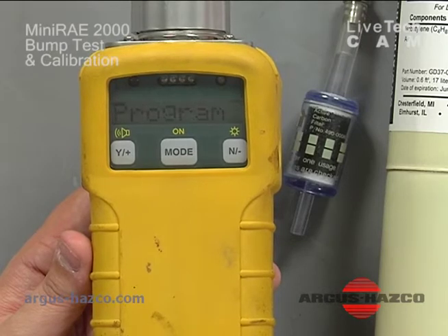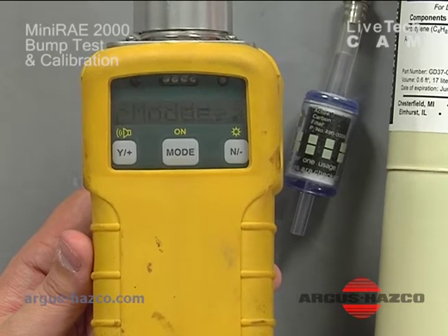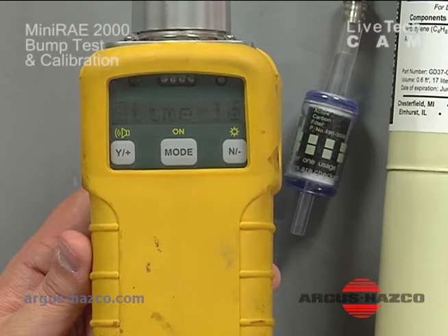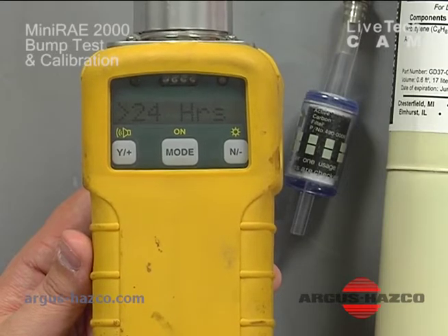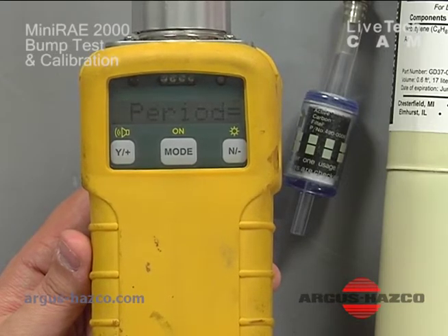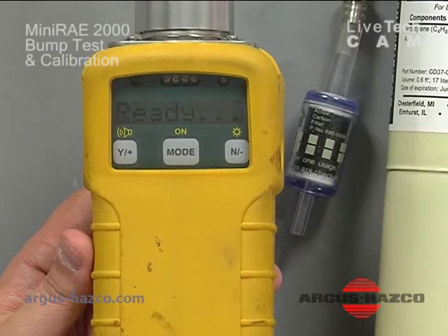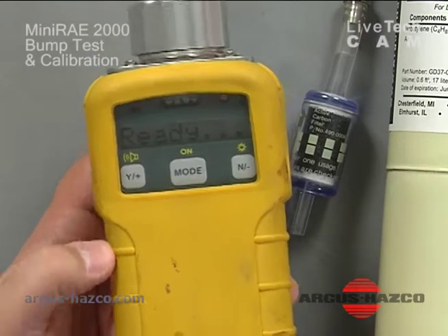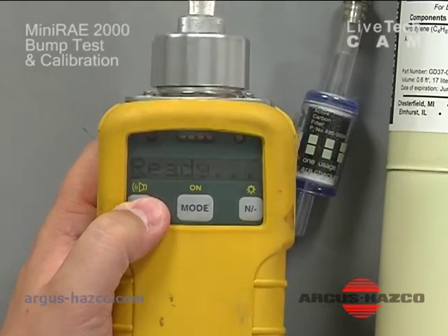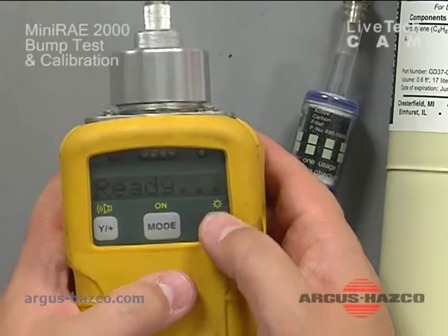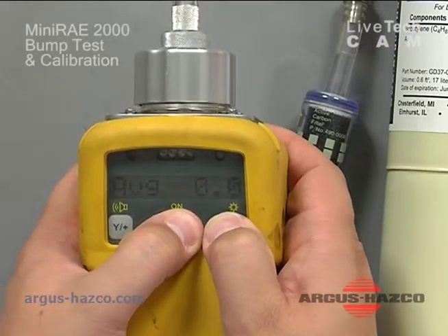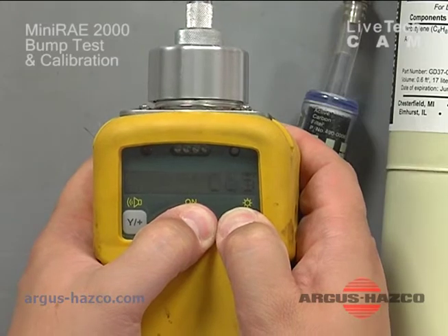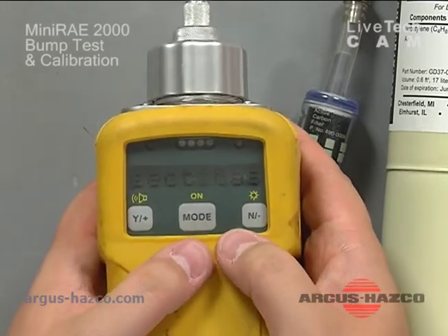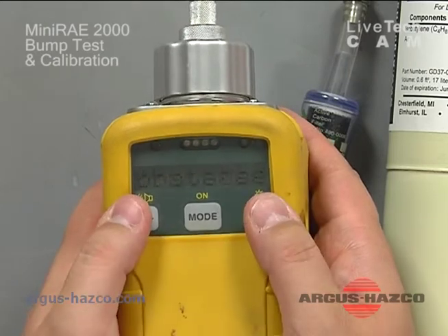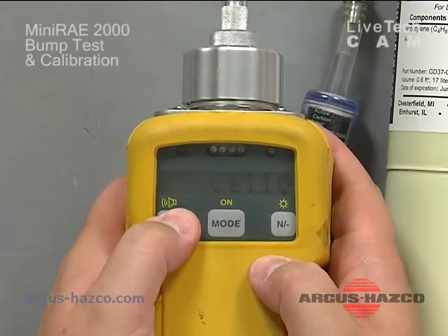The user mode is in program. The alarm mode is in auto reset, so if it hits alarm and drops below that, it will automatically reset. The data log time left is 24 hours if your period is set at 60 seconds. It's going to click over and tell you it's ready to go. You can either hit yes and go in and start your monitoring, or at this point we want to do a fresh air 0. So you take your no minus button and your mode button, and press and hold those together for a few seconds. You'll see a screen come up saying calibrate/select gas. It's asking yes or no, do you want to do that? Yes, we want to calibrate, so we select yes.